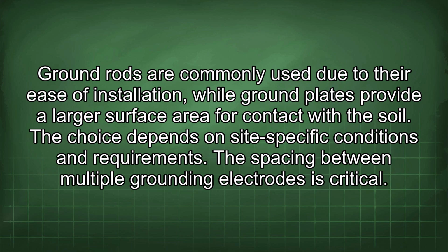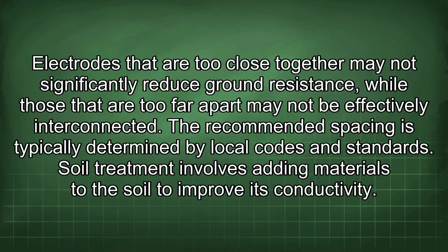The spacing between multiple grounding electrodes is critical. Electrodes that are too close together may not significantly reduce ground resistance, while those that are too far apart may not be effectively interconnected. The recommended spacing is typically determined by local codes and standards.